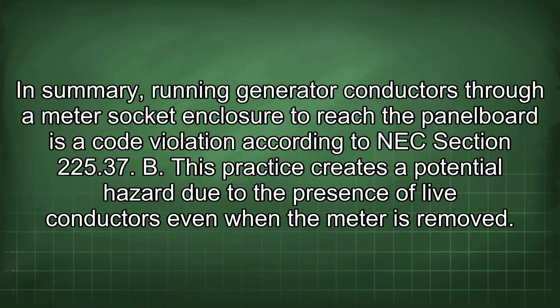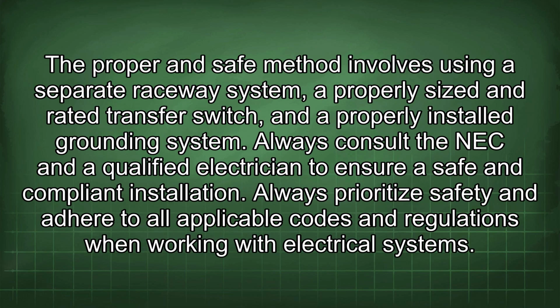A qualified electrician has the knowledge, skills, and experience necessary to safely and reliably connect a generator to a panel board. In summary, running generator conductors through a meter socket enclosure to reach the panel board is a code violation according to NEC Section 225.37(B). This practice creates a potential hazard due to the presence of live conductors even when the meter is removed. The proper and safe method involves using a separate raceway system, a properly sized and rated transfer switch, and a properly installed grounding system. Always consult the NEC and a qualified electrician to ensure a safe and compliant installation.